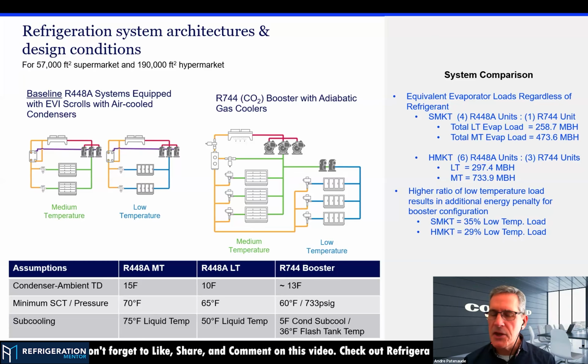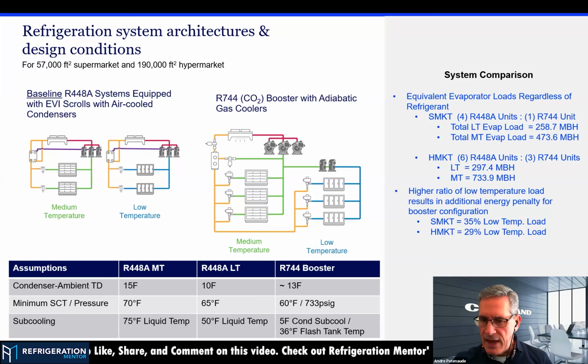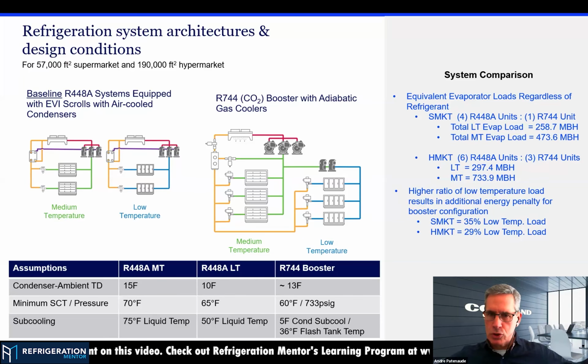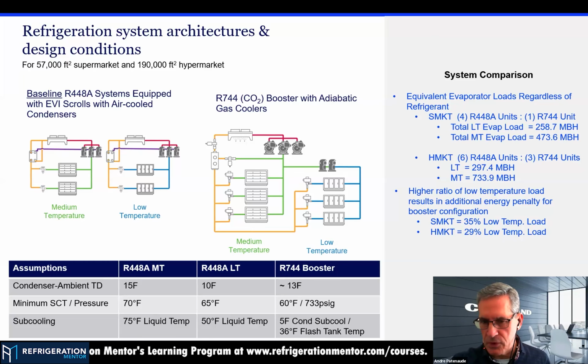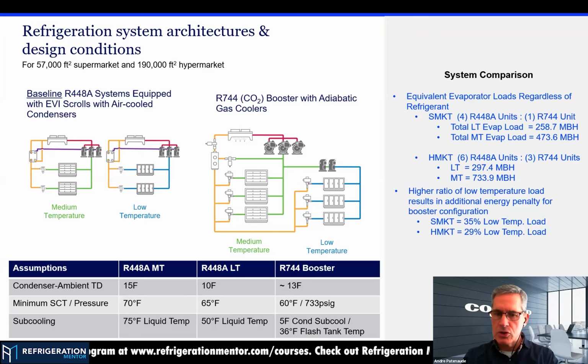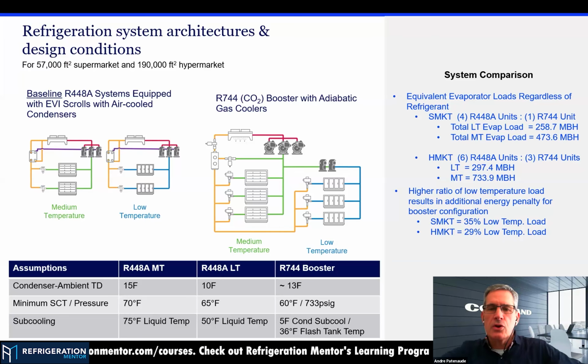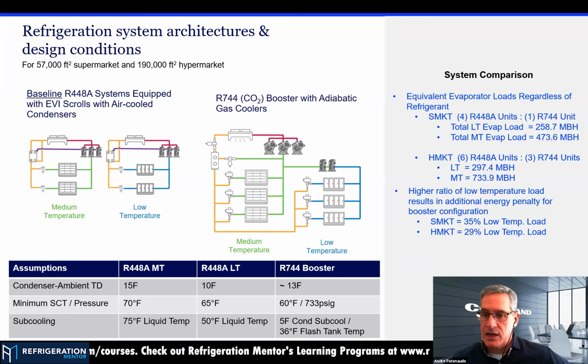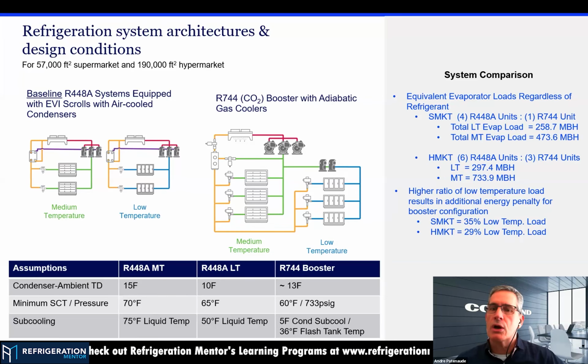And now that creates a dynamic that you're going to see later on, that supermarket, when we look at total percentage of low temp load to total system load, is 35%. And hypermarket is only 29. If we look at the CO2 system, for example, when I've got 35% of my total low temp load discharging into the medium temp suction, that has an impact on efficiency, because now your whole medium temp compressors have to manage 35% of the total system load coming from the low temp. I bring this up because when you look at energy numbers later, it'll have an impact.